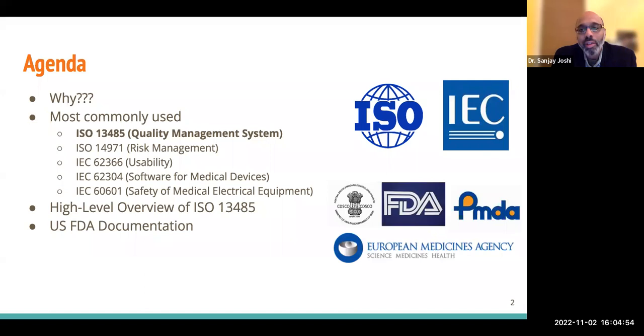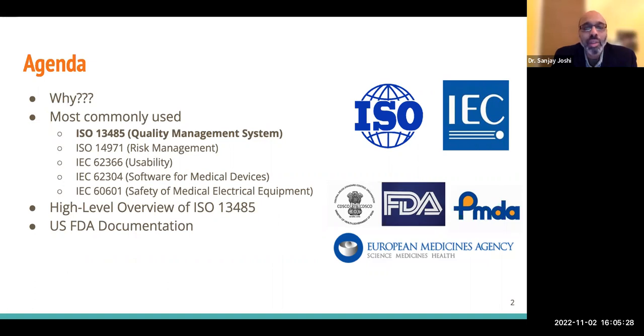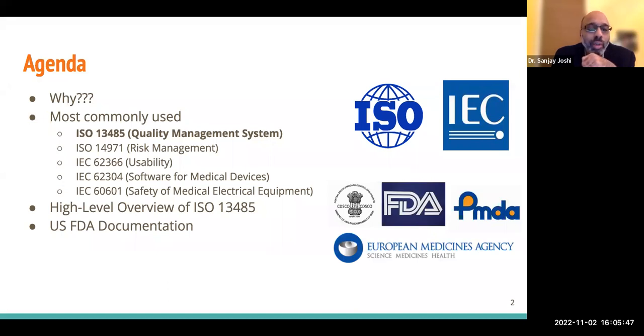You will hear the words ISO or IEC. They are used by multiple regulatory agencies — in India it is CDSCO, in the US it is FDA, in Japan it is PMDA, and in the European Union it's the European Medicines Agency. There are a lot of standards, and I have listed five of the most commonly used. Today we are going to look at the high-level overview of ISO 13485 — almost always it is the first standard you will hear or implement in your organization. The US FDA has a slightly different code called QSR, Quality System Regulation, with some minor differences that bring clarification to what ISO 13485 wants you to do.